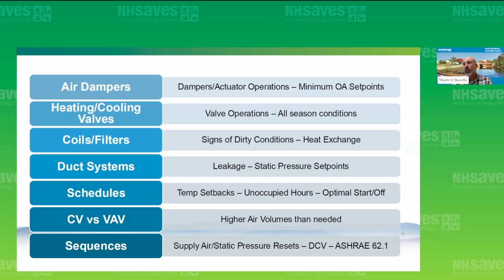So again, if it was an older system, maybe they don't have reset schedules in there that can take advantage of real-time conditions to save energy with heating set points and cooling set points. Air flows can be reduced with downstream conditions being met by adding some CO2 sensors, demand control ventilation systems. And then there's been changes in code ventilation requirements.